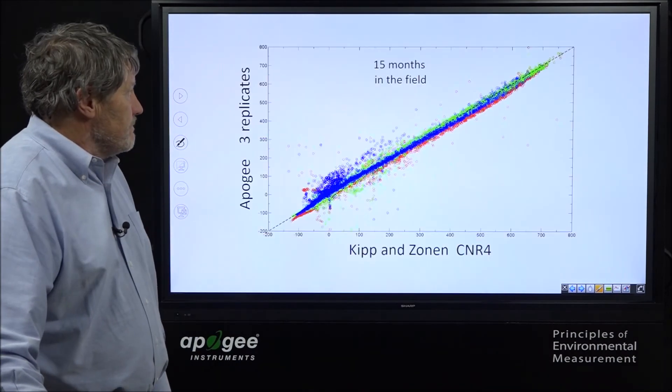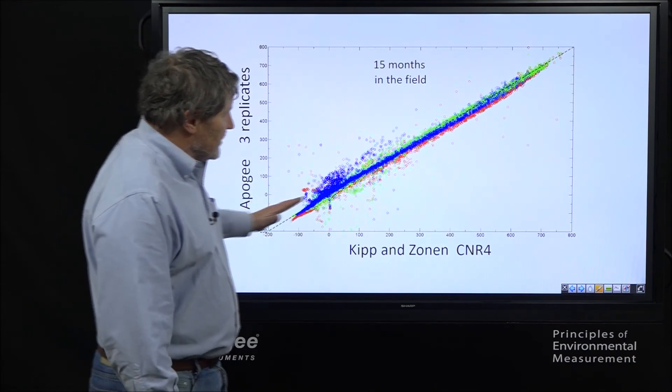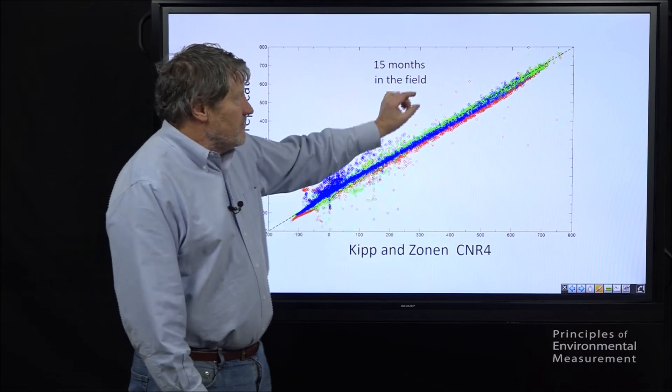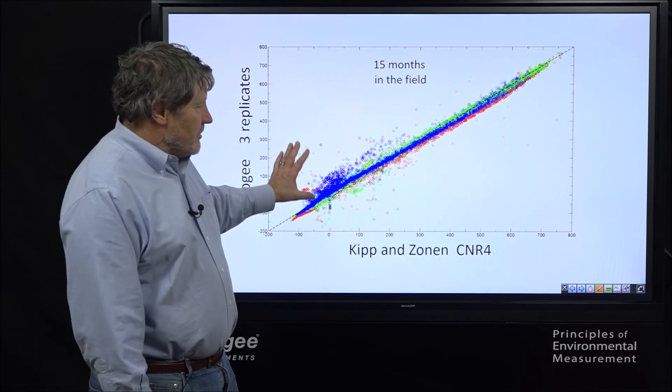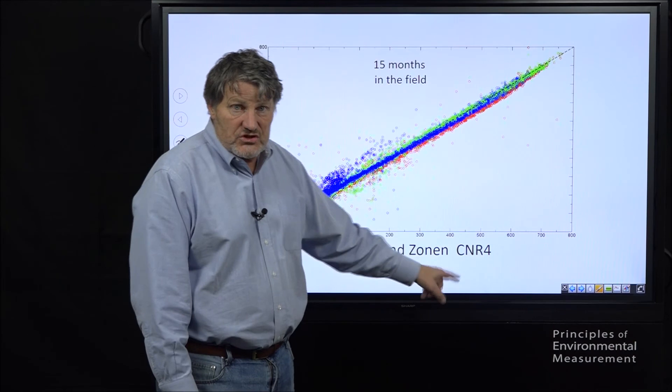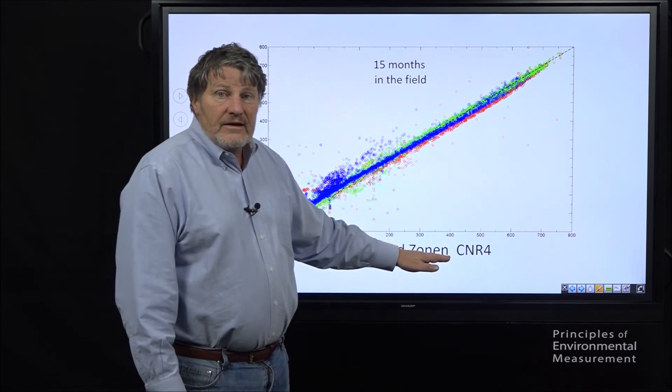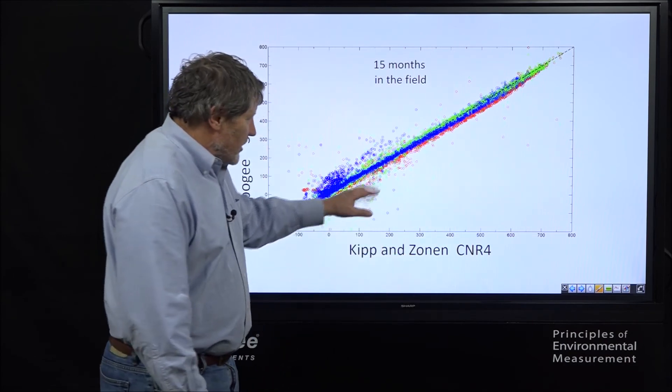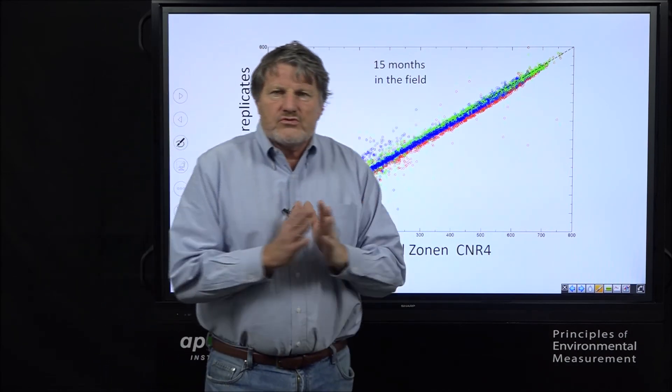here's the data. Here's the Kip and Zonen. Here's the Apogee, 15 months in the field. All of them track the Kip and Zonen very accurately. There's a few scattered points in here. And this is because something got on the sensor. Sometimes it got on the reference sensor and caused problems. This was not heated. This didn't have the heated shield. So, there are times when this had an error. But the point of this is we're very pleased with this accuracy.